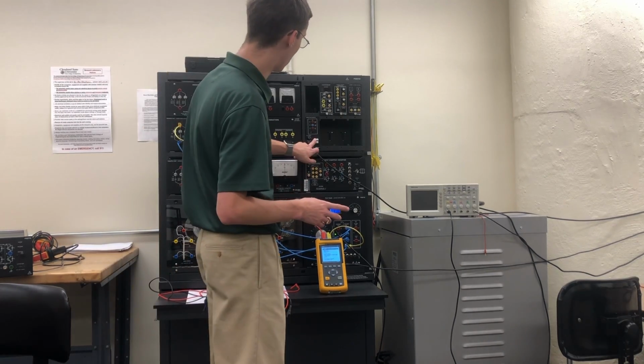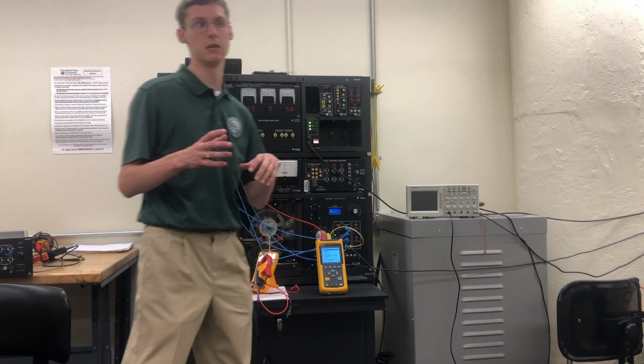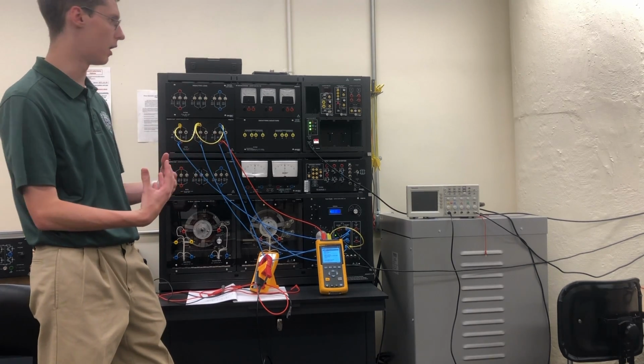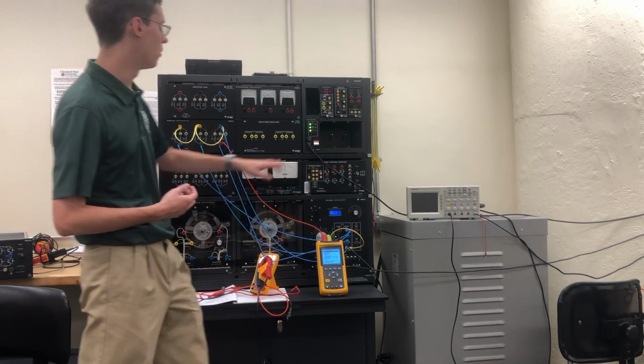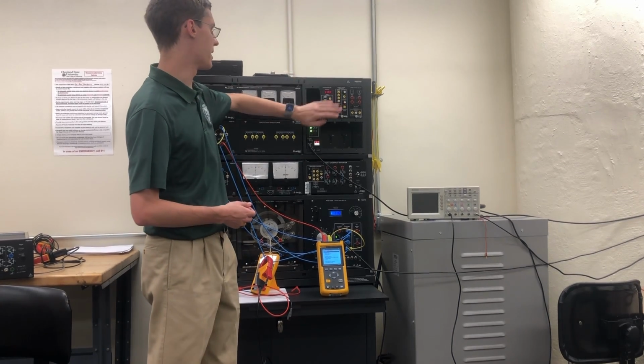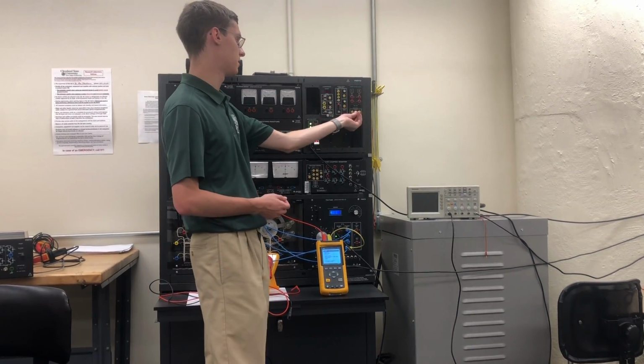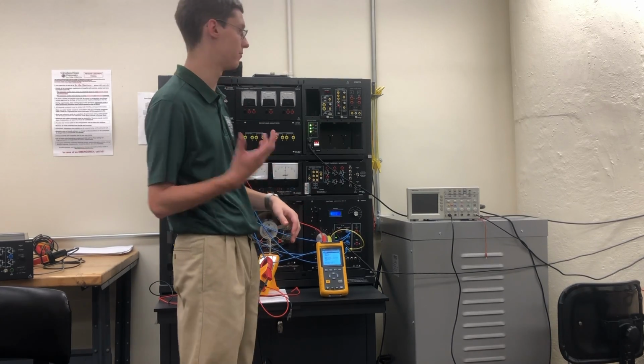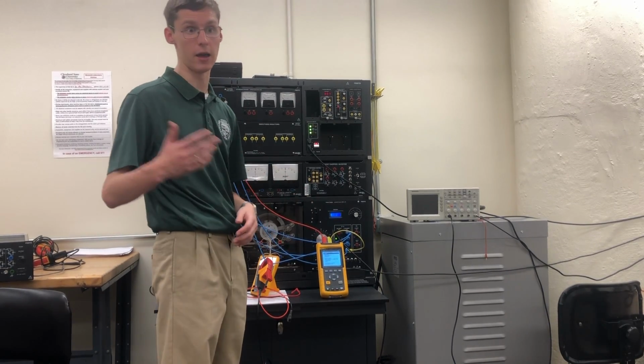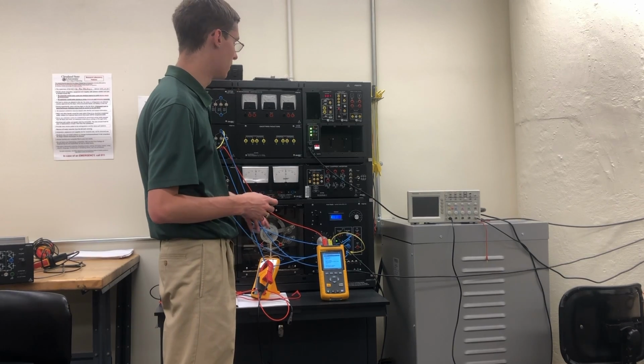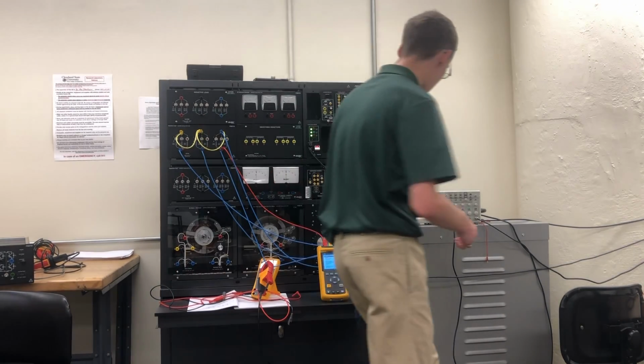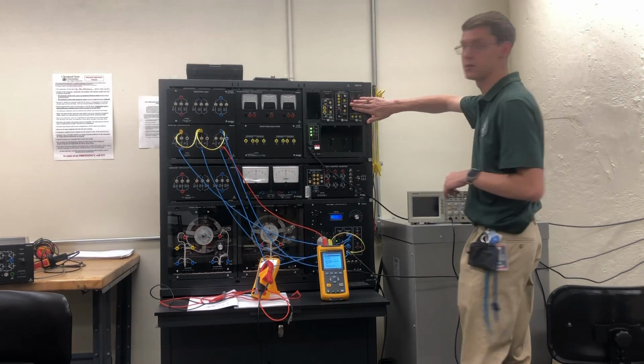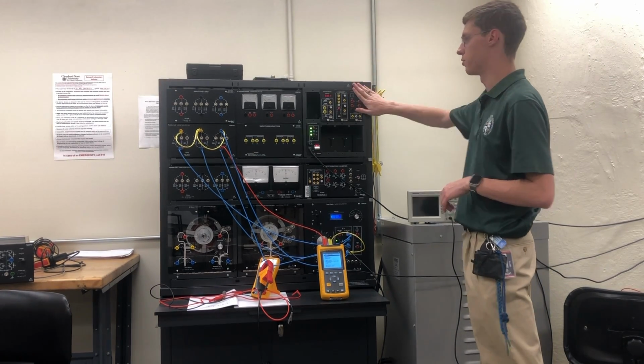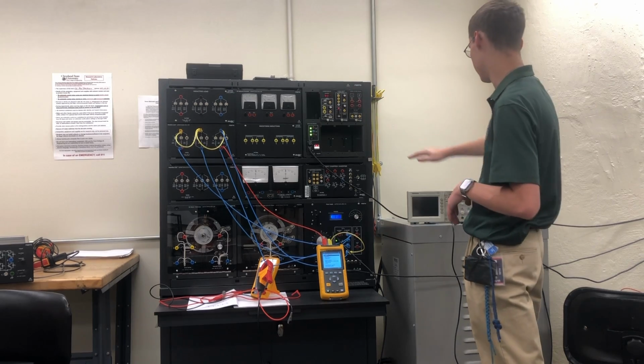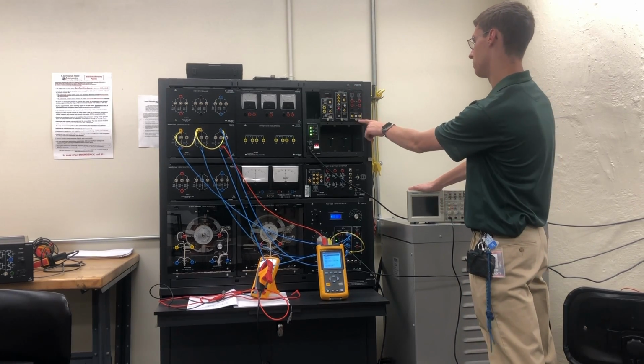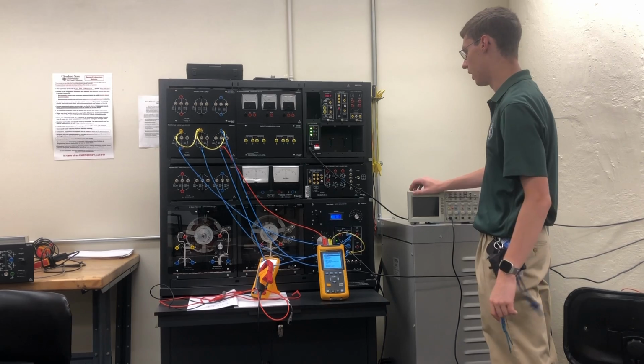Now, what you want to measure is actually you want to be able to see the waveform of your current or voltage. So that's where this unit comes in. Each of you should have these little plug-in units. They just screw in and plug in. So if you don't have a voltage isolator, just ask your TA, and he or she'll be able to provide it. So how this works, this isolates your scope from your unit. So you can supply 300 volts to this thing, and this will only see somewhere between 0 to 10 volts.